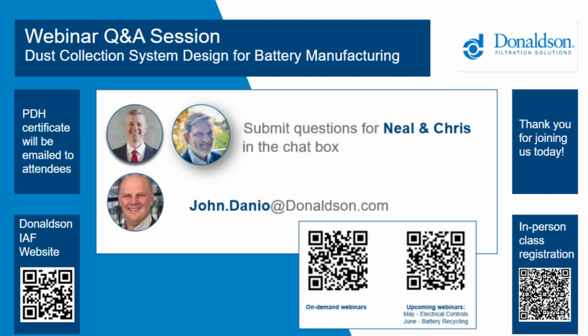And Donaldson's come a long way to helping our customers in that with the new smart collectors. So every collector we sell now comes with an IQ monitoring system where they can go in and set a dashboard that says, hey, once I've hit this certain differential pressure, I'd like to get a notification, and they'll get an email. Whoever at the plant is on that email chain will get a notification that says, hey, DC4 has reached high differential pressure. Someone needs to go make some changes to the controls. And that's eliminated a lot of the troubleshooting back and forth.